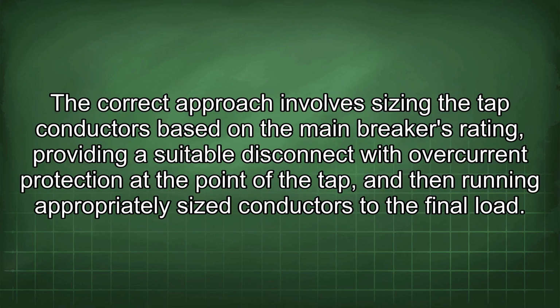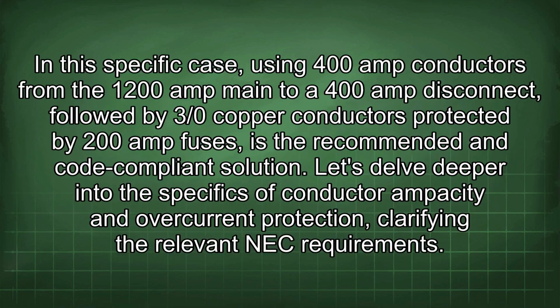The correct approach involves sizing the tap conductors based on the main breaker's rating, providing a suitable disconnect with overcurrent protection at the point of the tap, and then running appropriately sized conductors to the final load. In this specific case, using 400 amp conductors from the 1200 amp main to a 400 amp disconnect, followed by 3/0 copper conductors protected by 200 amp fuses, is the recommended and code-compliant solution.